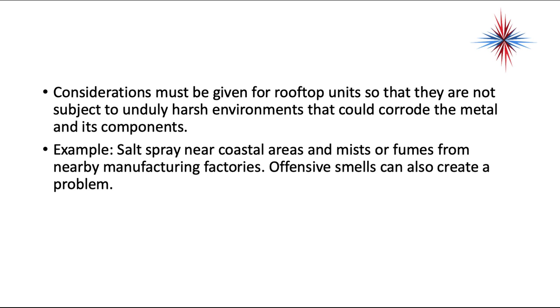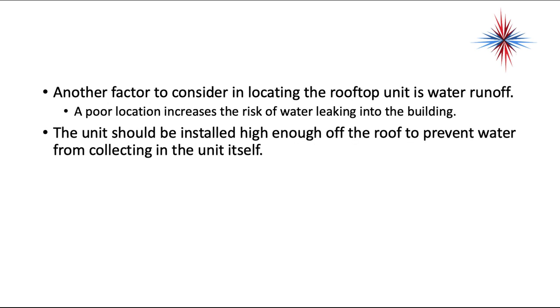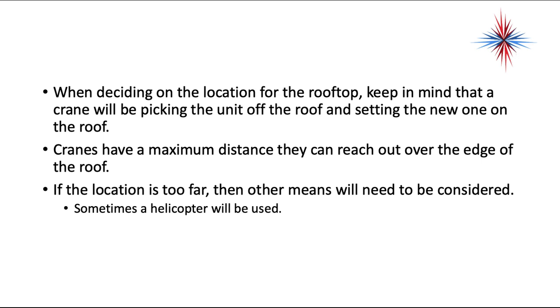Offensive smells can also cause problems because most rooftop units pull in outside air through their economizers. Another factor to consider in locating the rooftop unit is water runoff. A poor location increases the risk of water leaking into a building. You will have condensate that has to go someplace. The unit should be installed high enough off the roof to prevent water from collecting in the unit itself.